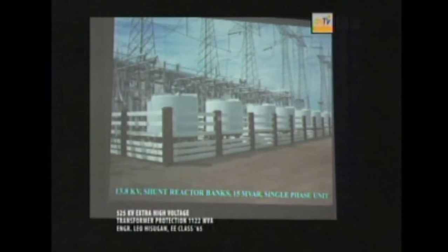On the 13.8 kV side of the transformer, we also utilize shunt bank reactors for overvoltages in the line. So we connect these shunt reactor banks on the 13.8 kV side of the delta tertiary, and then close them to lower voltages in a very long transmission line. Our 525 kV system is like 100 kilometers from one station to the other, or 150 kilometers.